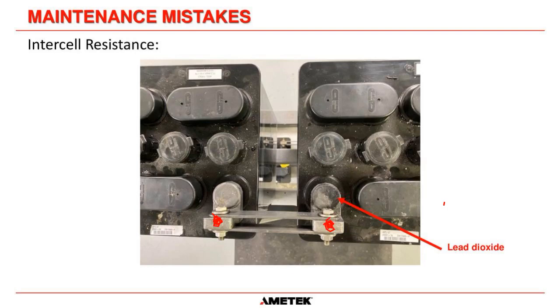Basically what we want to know is the resistance of the connection between these two jars. That is the intercell resistance, and that's a very important measurement to take, because if you have a high resistance connection between two batteries, that's going to heat up, cause losses, and cause your battery to not be able to give you the full power that you require.